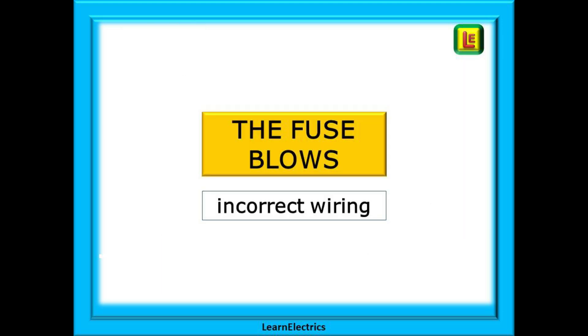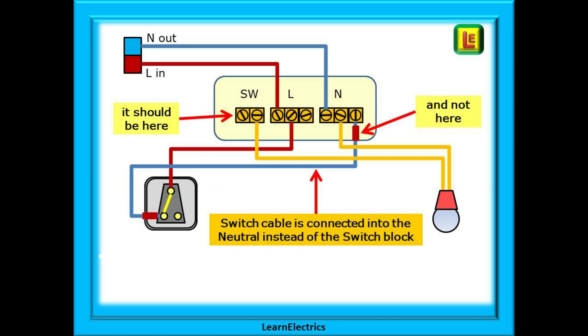This next one — the fuse blows — is often the result of incorrect wiring. You will come across this in a work day situation, but not many assessors will deliberately put this as a live fault because of the excessive currents that flow. The switch cable coming from the switch and going back to the ceiling rose has not been terminated into the switch block; whoever's done it has terminated it into the neutral block. The result is that every time the switch is turned on there is a direct short across line and neutral — the fuse will blow, the breaker will trip. This is often a result of a lack of knowledge, the person assuming that all blue wires are neutrals. This is why electricians mark the ends of the switch cable with brown sleeving as an indicator that this is not a neutral conductor.